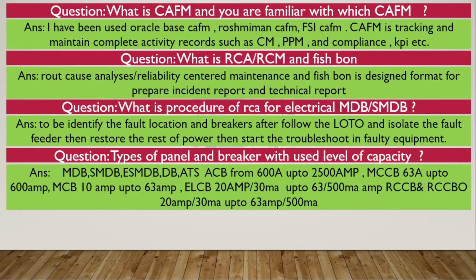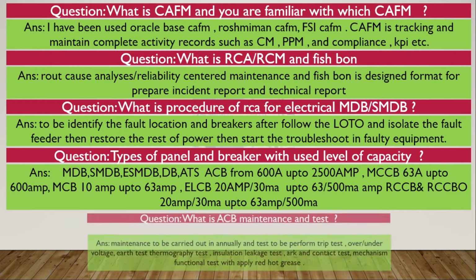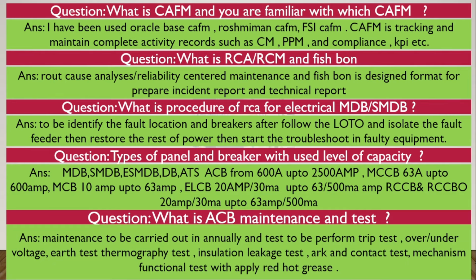ELCB has one important thing: earth leakage circuit breaker, 20 amps to 30 milliamps, up to 63 amps to 500 milliamps. RCCB, residual current circuit breaker, and RCCBO, residual current circuit breaker with overload, which can be used from 20 ampere 30 milliamps up to 63 ampere 500 milliamps. That's it. So what is the ACB maintenance and test?